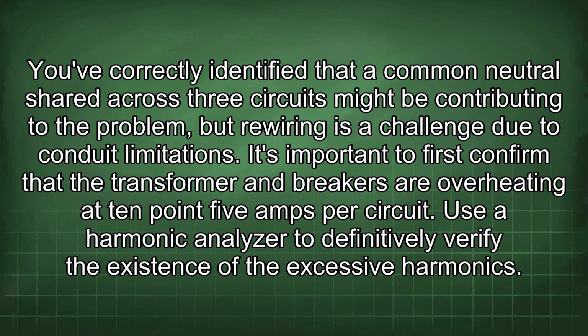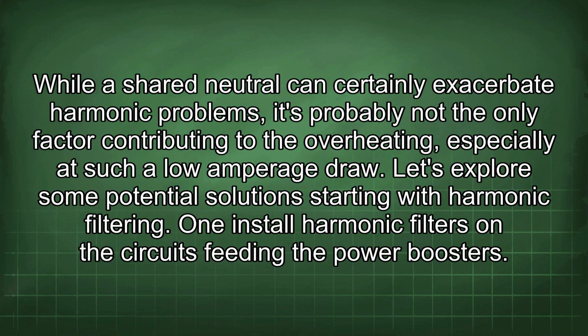It's important to first confirm that the transformer and breakers are overheating at 10.5 amps per circuit. Use a harmonic analyzer to definitively verify the existence of the excessive harmonics. While a shared neutral can certainly exacerbate harmonic problems, it's probably not the only factor contributing to the overheating, especially at such a low amperage draw. Let's explore some potential solutions, starting with harmonic filtering.